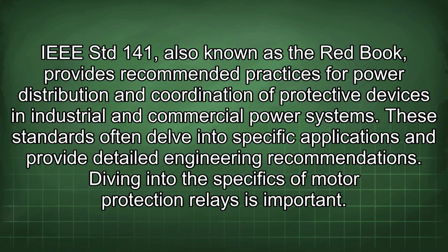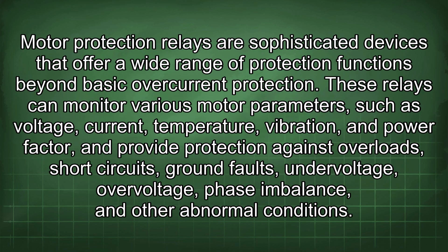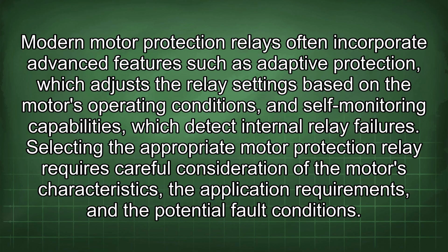Diving into the specifics of motor protection relays is important. Motor protection relays are sophisticated devices that offer a wide range of protection functions beyond basic overcurrent protection. These relays can monitor various motor parameters such as voltage, current, temperature, vibration, and power factor, and provide protection against overloads, short circuits, ground faults, undervoltage, overvoltage, phase imbalance, and other abnormal conditions. Modern motor protection relays often incorporate advanced features such as adaptive protection, which adjusts the relay settings based on the motor's operating conditions, and self-monitoring capabilities, which detect internal relay failures.